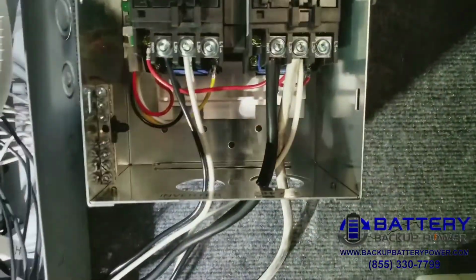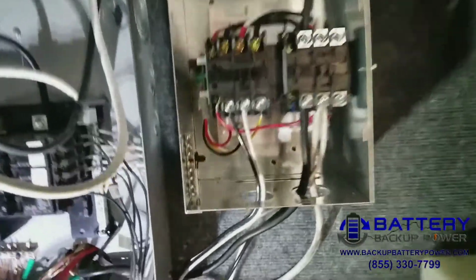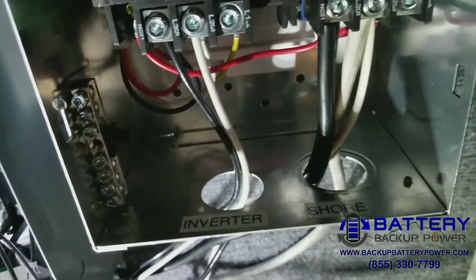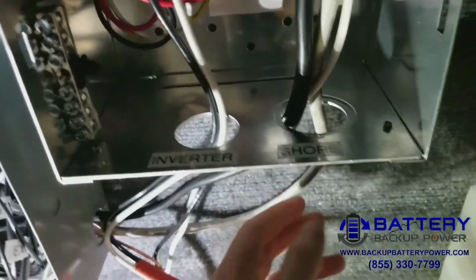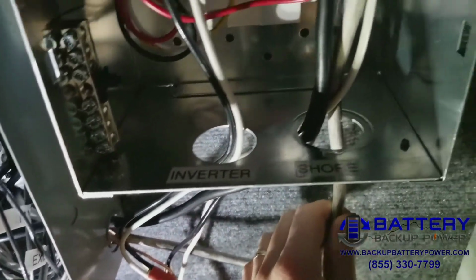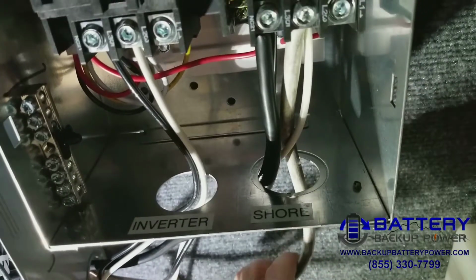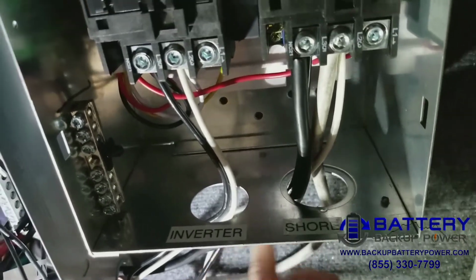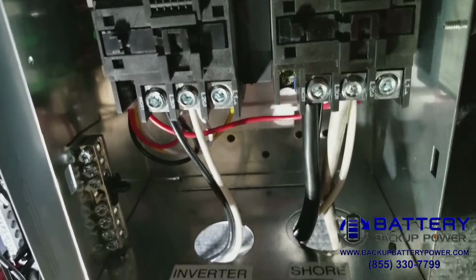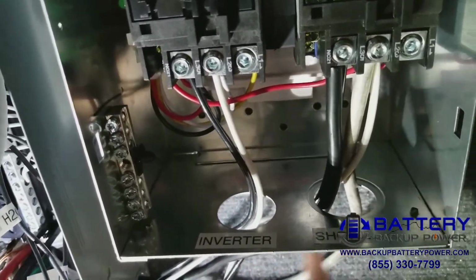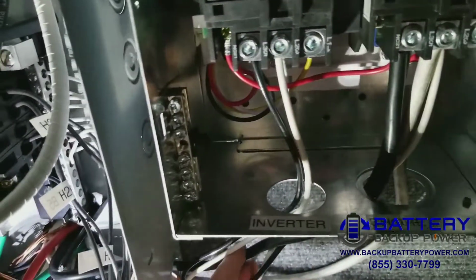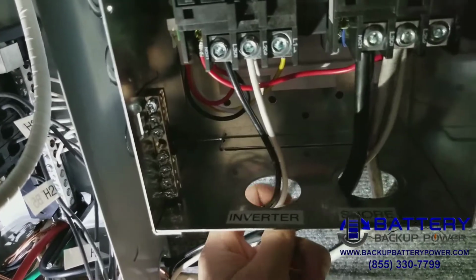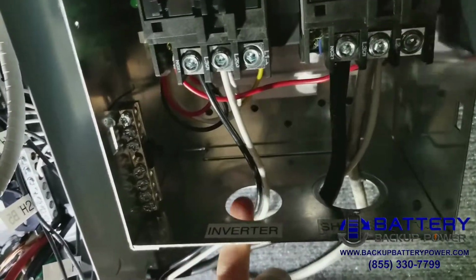The reason you use an automatic transfer switch is to allow you to have a secondary source of power. So in this case, when the trailer is plugged in, or say you have a building with utility power, everything is running off utility power. If utility power fails, it should automatically switch over to an inverter or generator. In this case, we have an inverter running off a battery bank.